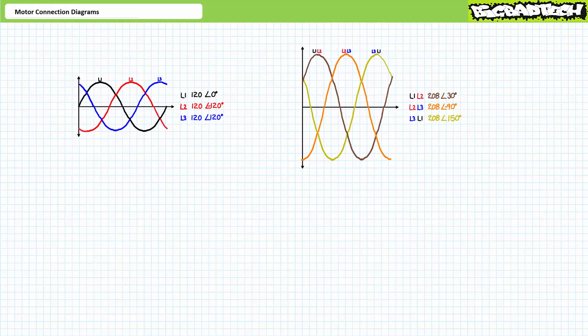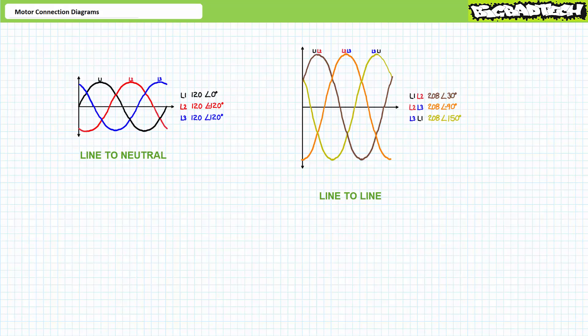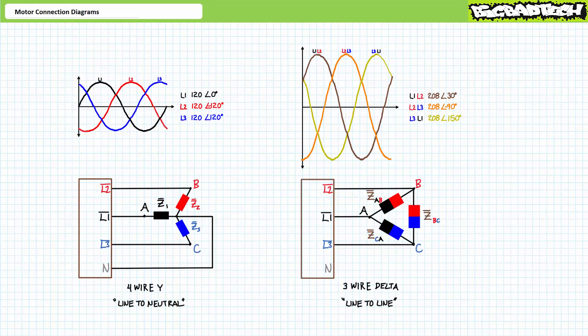First among our tasks is to have a working description of three-phase AC and define the term dual voltage. Three-phase AC is characterized by three sinusoidally oscillating waveforms with equal magnitude and frequency, phase shifted from one another by a relative 120 degrees. A single three-phase AC system in effect offers a choice of two voltages: the lower line-to-neutral voltage and the higher line-to-line voltage. Line-to-line voltage is always square root three, or roughly 1.73 times, that of line-to-neutral. Light industrial three-phase AC inside the United States is characterized by a 120-volt line-to-neutral and a 208-volt line-to-line value. Three-phase AC allows two basic options: Y-configured loads, which experience the lower line-to-neutral voltage, and delta-configured loads, which experience the higher line-to-line voltage.